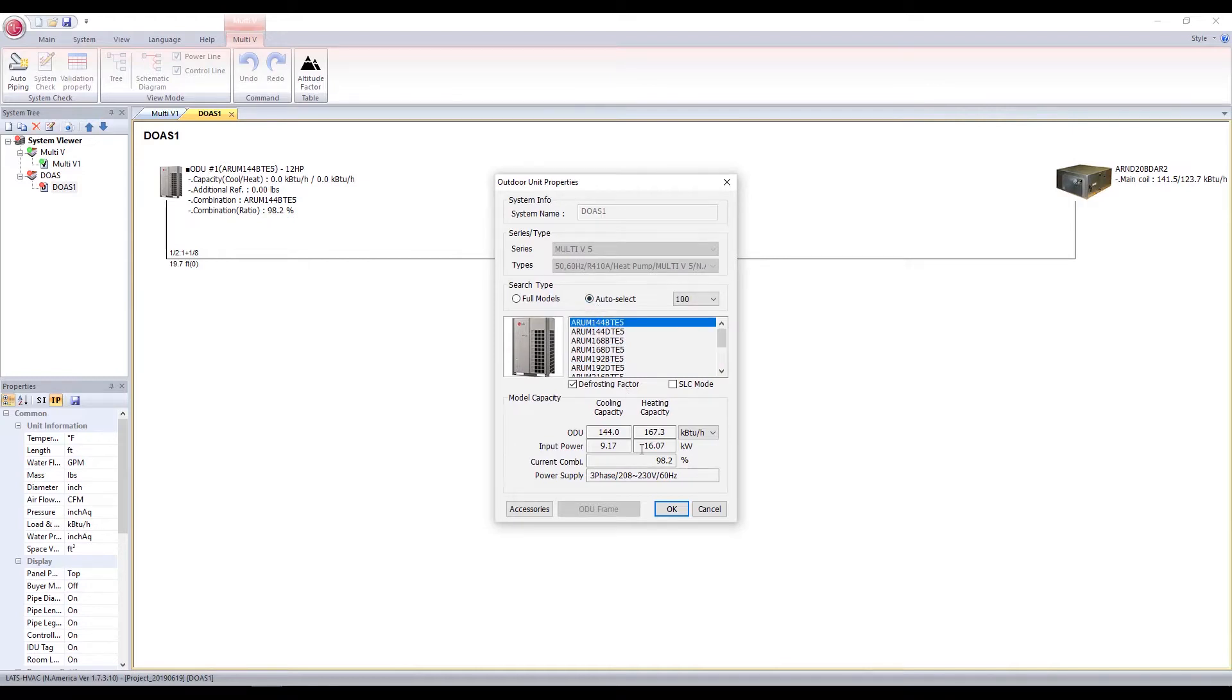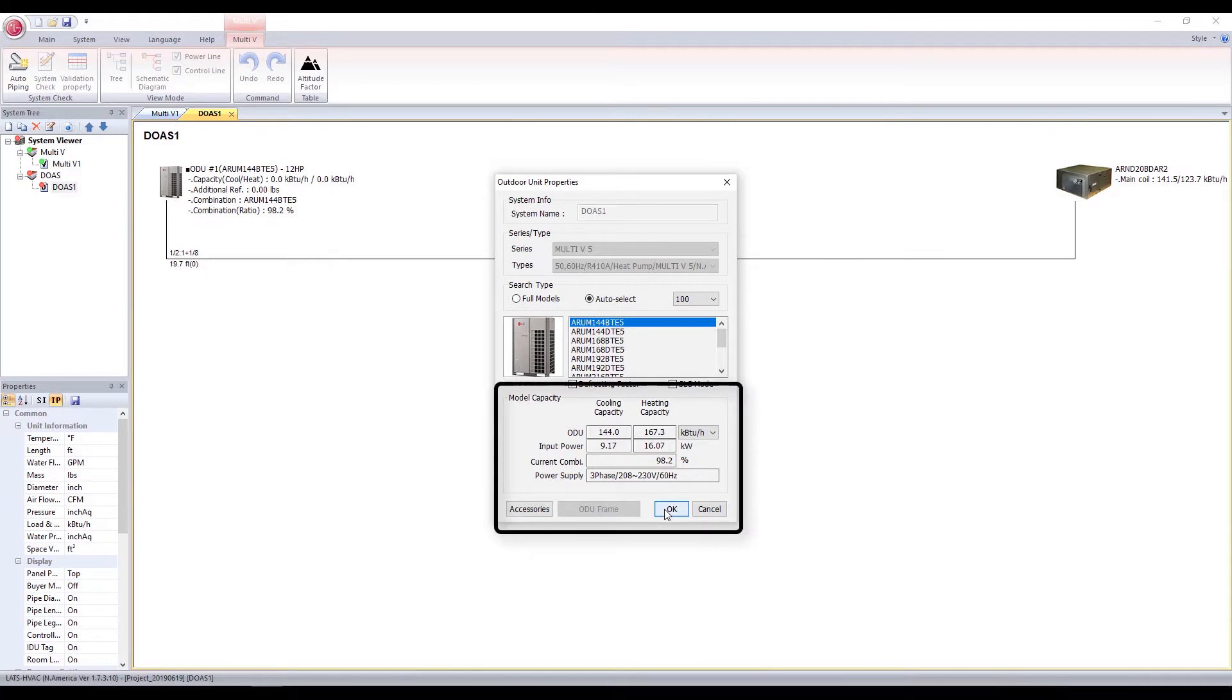The program will automatically select a model based on the combination ratio. It is the ratio of total IDU capacity to ODU capacity. The recommended combination ratio for DOAS is in the range between 50 and 100%.